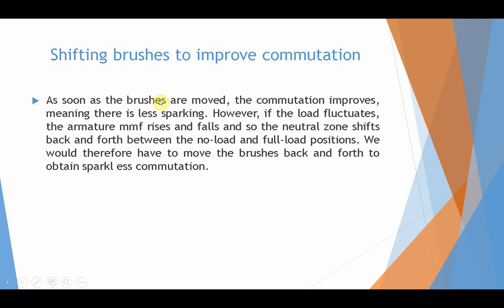Shifting brushes improves commutation, meaning there is less sparking. However, if the load fluctuates, the armature MMF rises and falls, and so the neutral zone shifts back and forth between the no-load and full-load position. We would therefore have to move the brushes back and forth to obtain sparkless commutation.